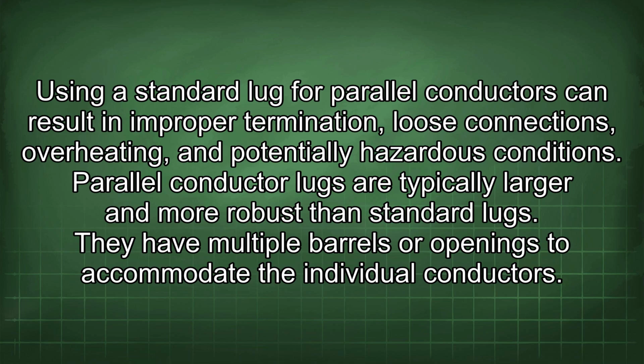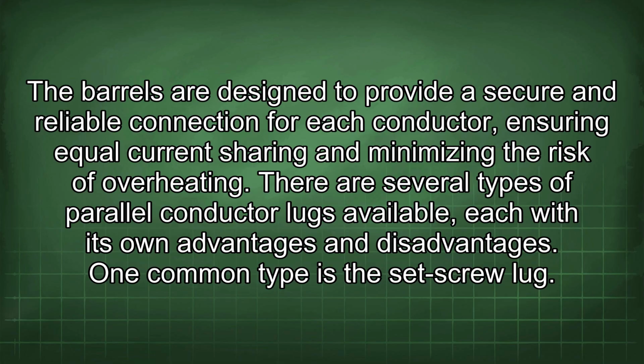Parallel conductor lugs are typically larger and more robust than standard lugs. They have multiple barrels or openings to accommodate the individual conductors. The barrels are designed to provide a secure and reliable connection for each conductor, ensuring equal current sharing and minimizing the risk of overheating. There are several types of parallel conductor lugs available, each with its own advantages and disadvantages.